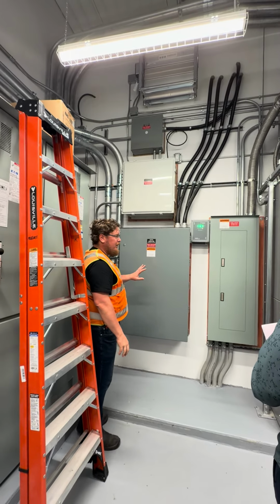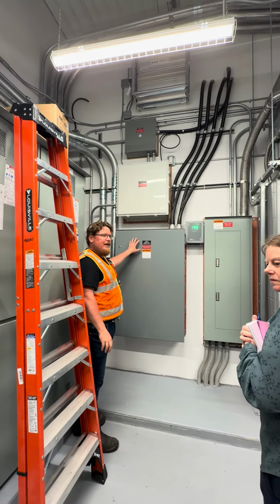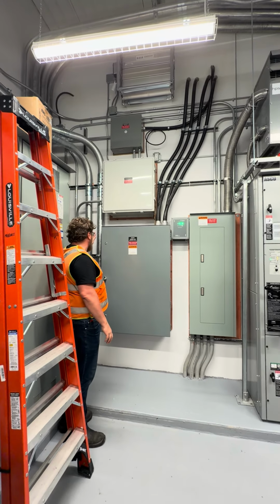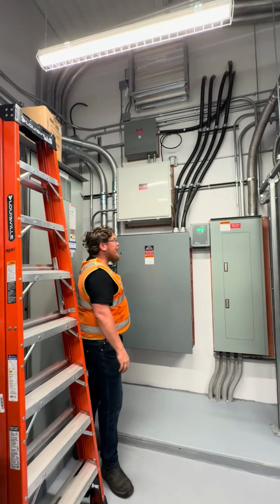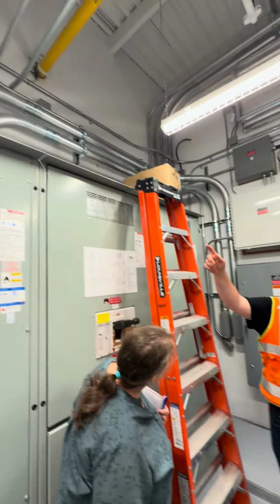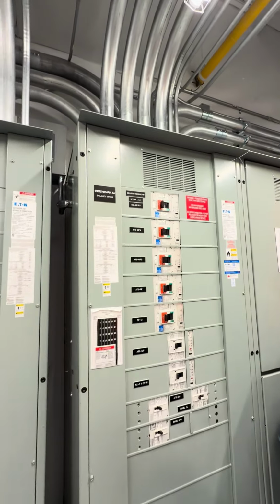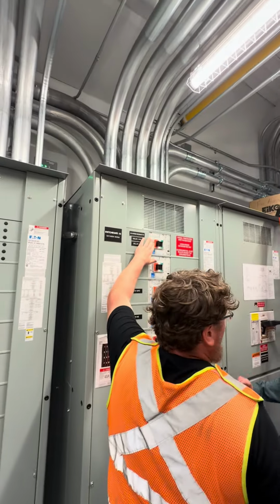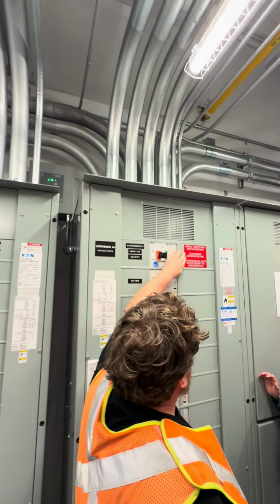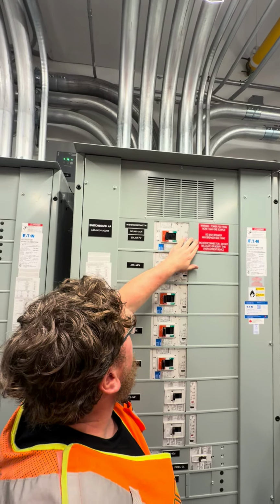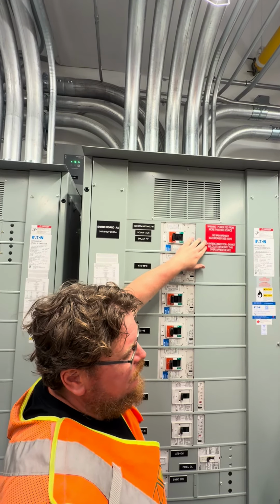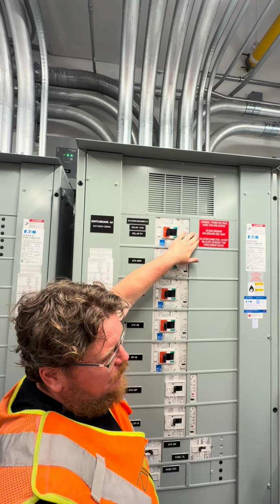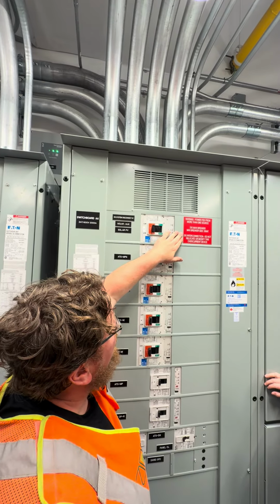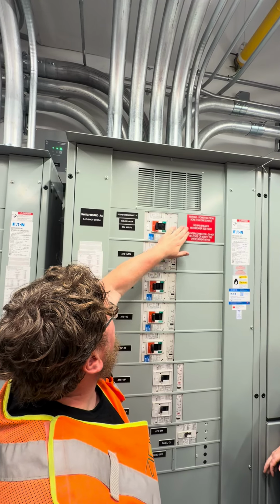So the power that went out the back of this disconnect goes in the back of the other disconnect, then comes back in through these two, and runs up into the switch gear to this breaker on the load side. There's some clear labeling here saying this is the DG, or distributed generation — the generic term for solar, wind, or battery energy. So this is the interconnection breaker.